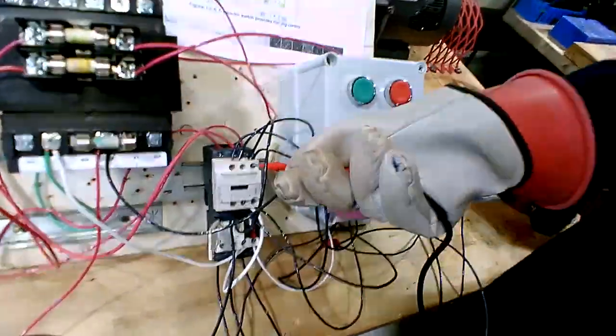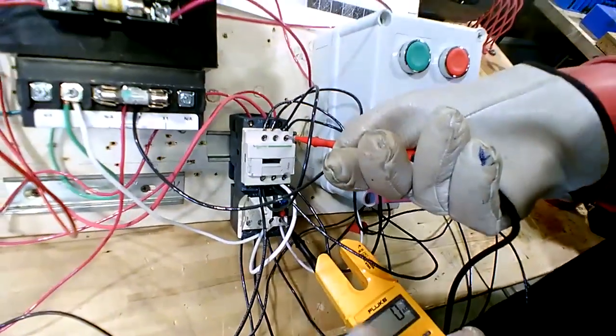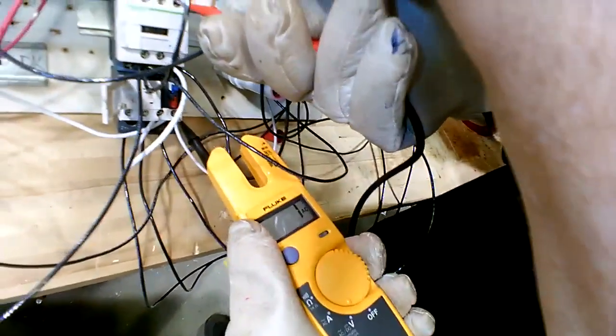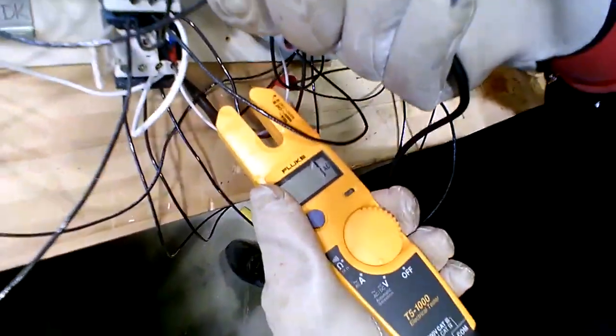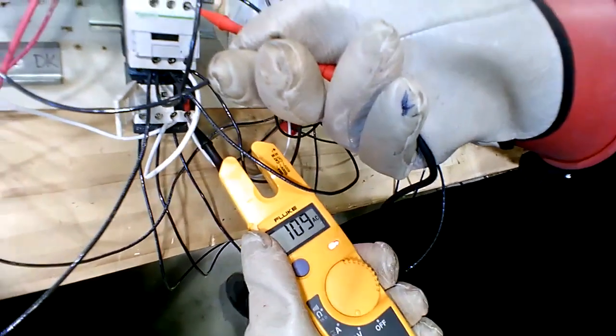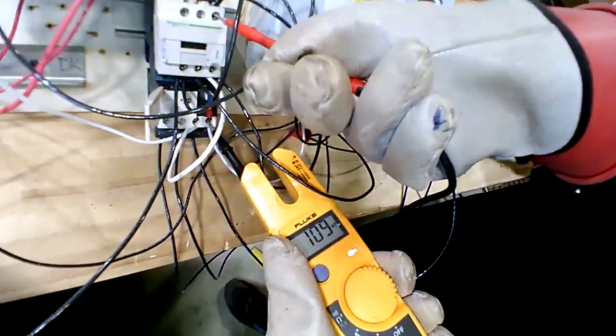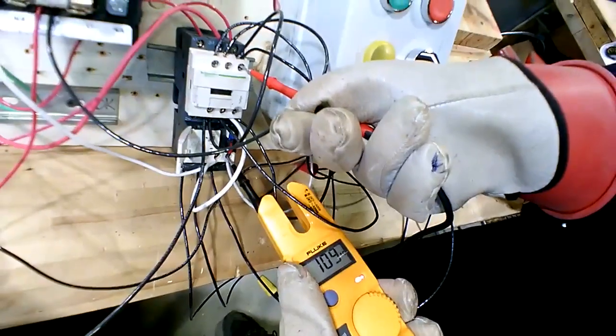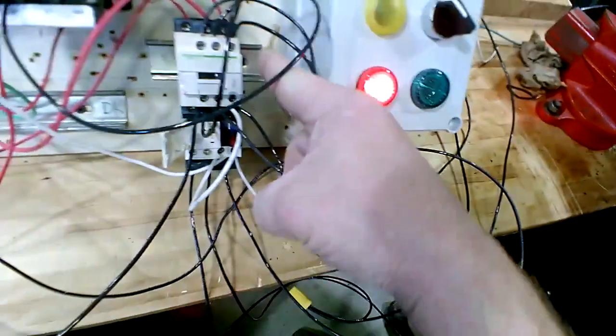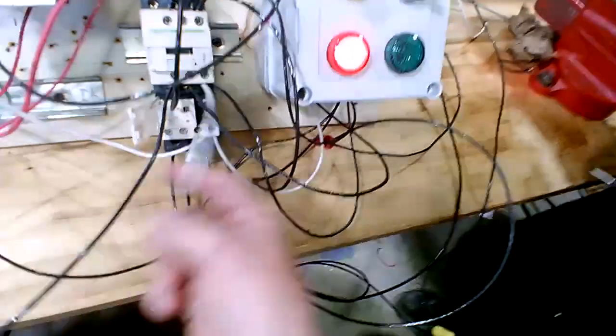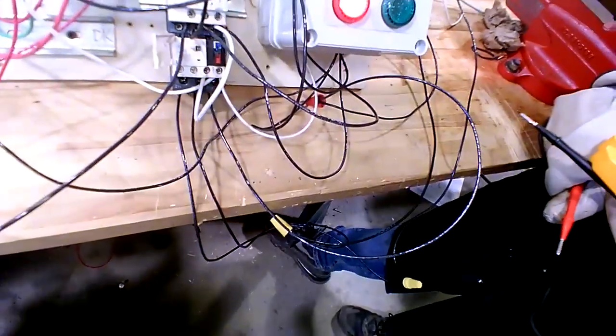So you got A1 and 96. Now, when I hold the button in, you get the signal. See there? So you're getting the signal there even whenever it trips. It's telling you that you're getting the power to the A1, but you've actually lost neutral, what you just proved there. Now you reset the blue button.